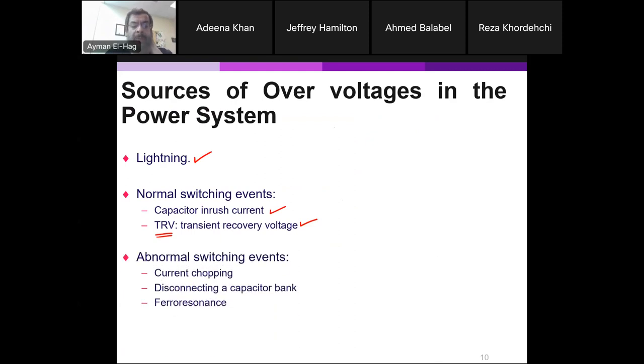Next week, we'll talk about something called abnormal switching events. These two are normal switching: connecting the capacitor bank is very normal, and clearing a fault with a breaker is also normal. But there are some abnormal ones, like what we call current chopping. Disconnecting a capacitor bank, we'll see the impact of this. Ferroresonance is a very important phenomenon that happens, especially in the distribution system, and its impact. Now these we'll talk about next week, plus how we can protect the power system from surges.